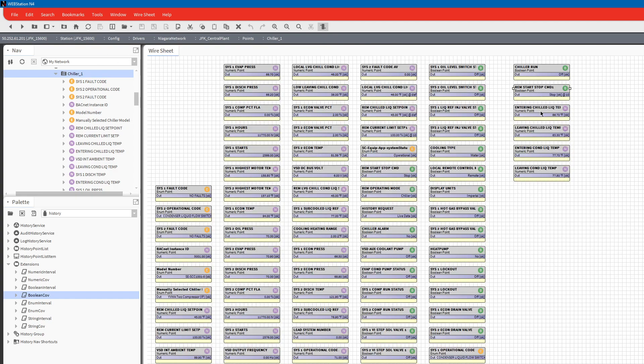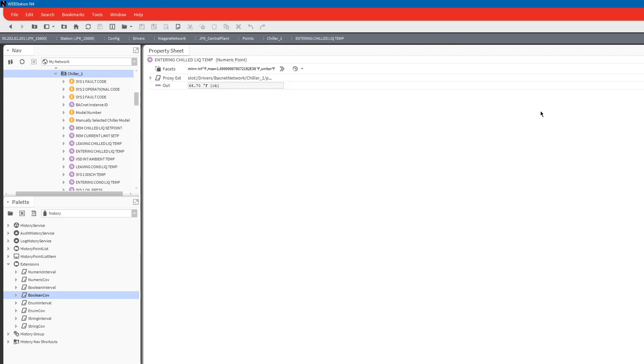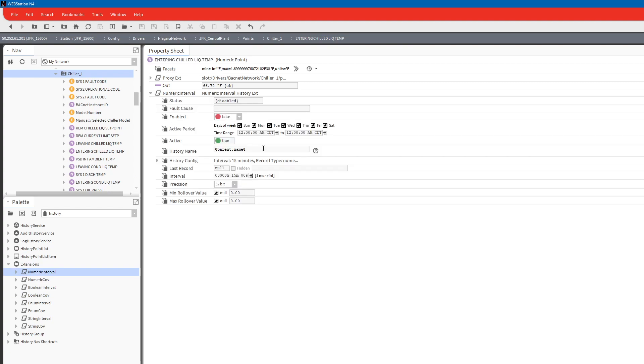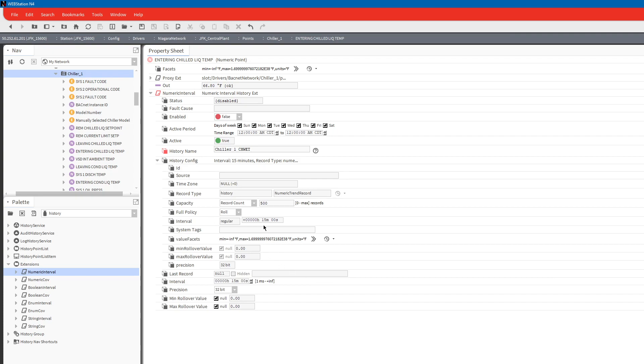I've already done the remote start stop command so let's go ahead and do entering chilled liquid temp. This is going to be a numeric, we could do interval or COV, interval's better. That's basically a snapshot over a time period. For this one we're going to say chiller one water entering temp history config.